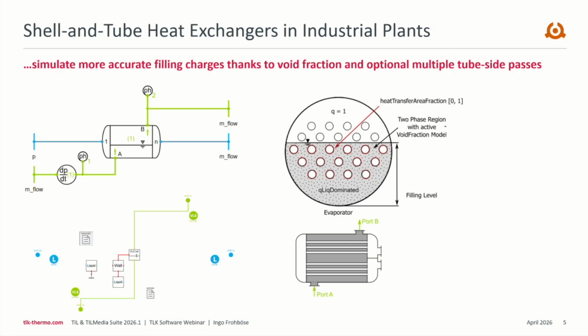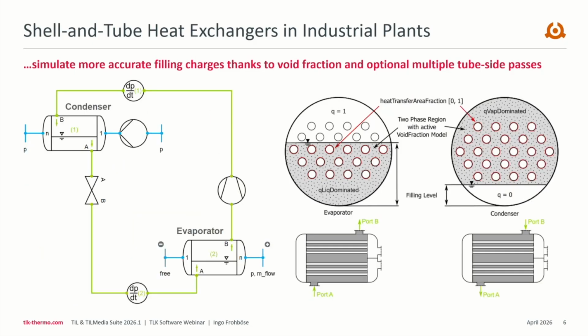And this filling level is also depending on the void fraction, which is occurring below the filling level. So here we typically have something like nucleate boiling and gas bubbles. And this also affects how much mass is in such a heat exchanger. Above the filling level in the evaporator, we have saturated vapor. And in the condenser model, it's the other way around. We have a vapor-dominated phase with droplets and a saturated liquid phase below the filling level. And these models are also robust and accurate in a closed system.